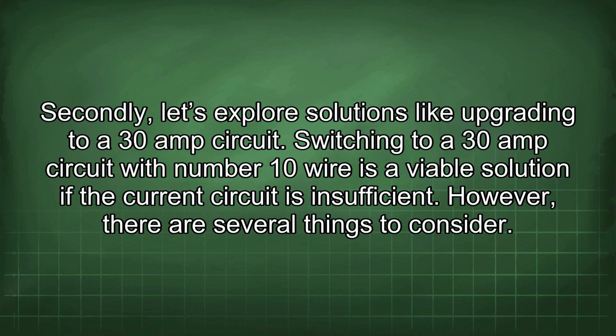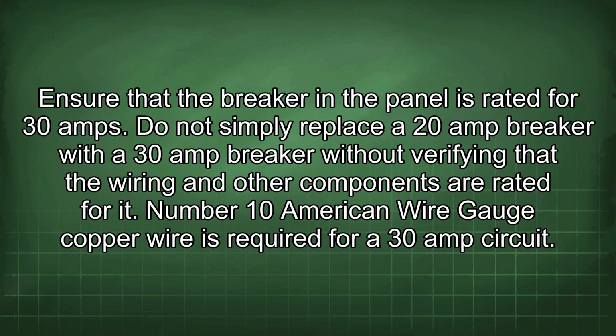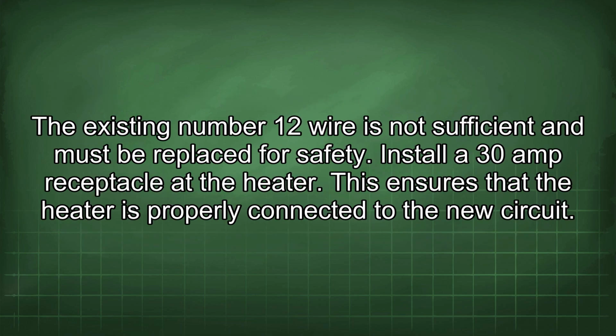Secondly, let's explore solutions like upgrading to a 30-amp circuit. Switching to a 30-amp circuit with number 10 wire is a viable solution if the current circuit isn't sufficient. However, there are several things to consider. Ensure that the breaker in the panel is rated for 30 amps. Do not simply replace a 20-amp breaker with a 30-amp breaker without verifying that the wiring and other components are rated for it. Number 10 American wire gauge copper wire is required for a 30-amp circuit. The existing number 12 wire is not sufficient and must be replaced for safety. Install a 30-amp receptacle at the heater. This ensures that the heater is properly connected to the new circuit.